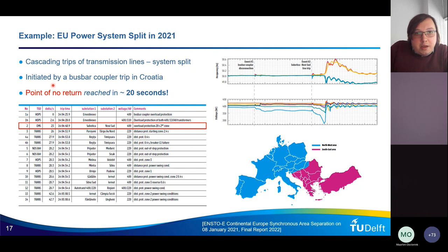Now, this was initiated by a busbar coupler trip in Croatia. And the point of no return: from the moment the physical disturbance happened until all the lines automatically started tripping across this border, we call this point, when they start tripping and the cascade is uncontrollable, the point of no return. From the moment of the initial disturbance until the point of no return was reached, it took around 20 seconds. So it's quite fast. Now, imagine that cyber attacks that could be distributed across Europe would have similar effects. So it can lead to cascading failures and a blackout.